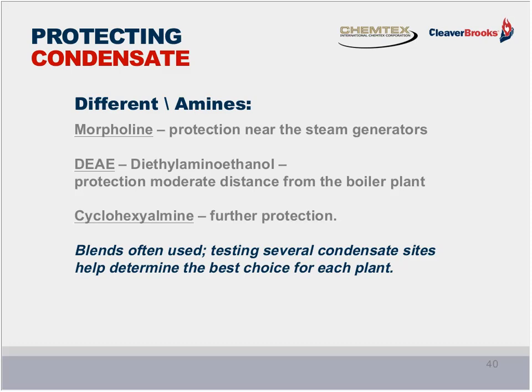And when you are doing your testing, you want to make certain that you're testing different condensate receivers around the plant, because only testing one receiver can oftentimes result in other areas of the plant not having condensate protection. But by the time all the condensate comes back to the boiler room, it's diluted by the properly treated condensate and the problems don't show themselves.